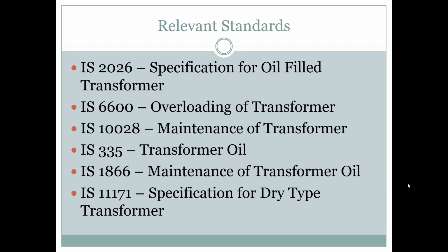IS 10028 is for maintenance of the transformer, how to maintain a transformer. Now, transformer oil is a very, very interesting subject. It is a subject by itself within transformers. That's why you find there are two ISs. One is for transformer oil, the new oil. That means when you buy oil. Here also an interesting point is that in India, for 1,500 plus transformer manufacturers, there are only two transformer oil suppliers. You will not believe it. Apar and Savita. Just imagine how the transformer manufacturers run around to get supply from them.